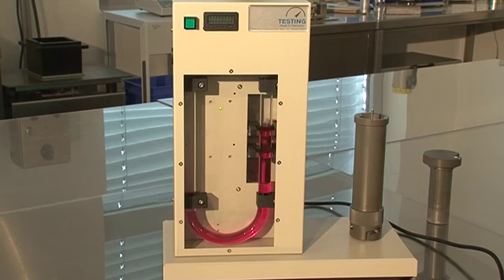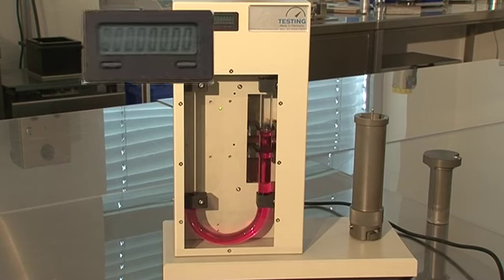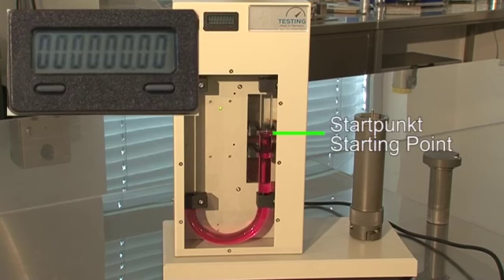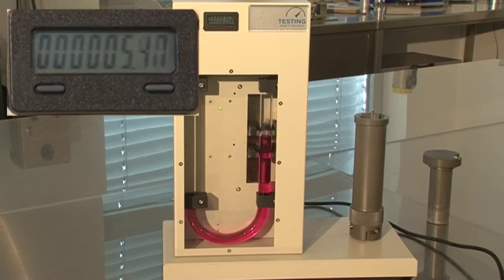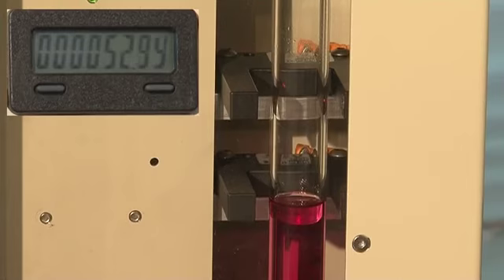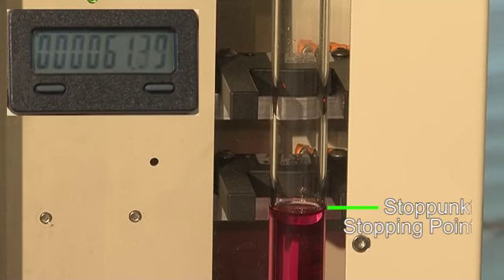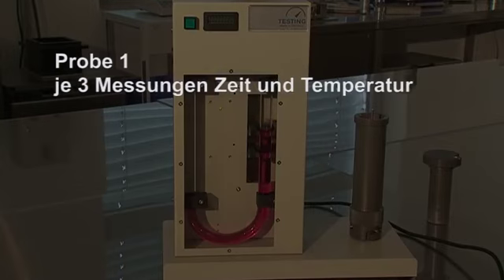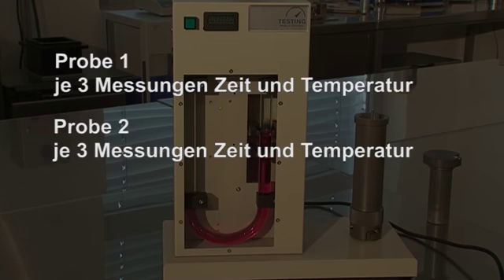Briefly press the start button to test it. The manometer liquid is sucked in. Once the required level has been reached, the pump stops. The oil level drops slowly. On reaching the upper light barrier, the time measurement begins. This runs automatically. The time measurement stops when it passes the lower light barrier. Three measurements are carried out for the reference substance. The temperature must also be recorded.